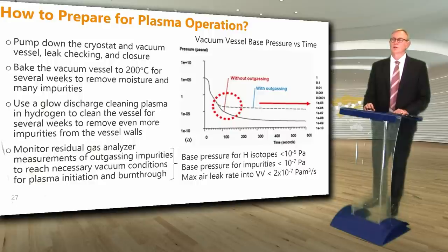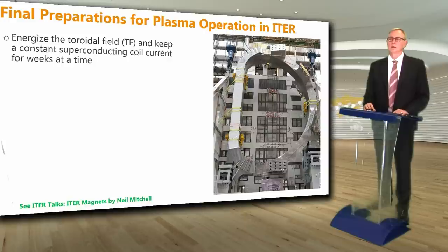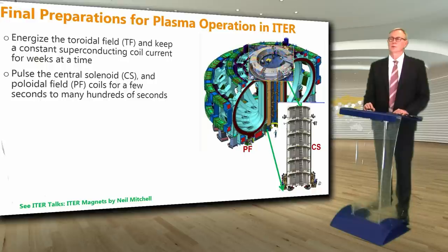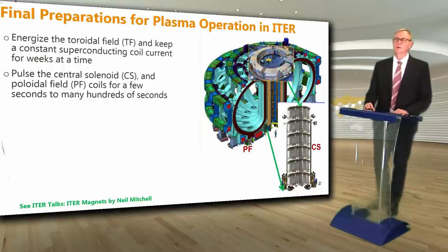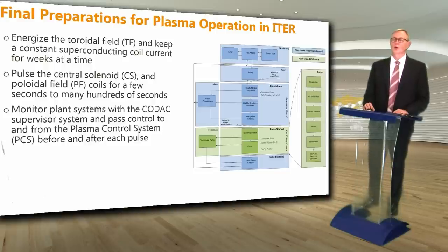This graph shows the vacuum vessel base pressure gradually decreasing with time as the vacuum conditions improve. The final preparations for plasma operation will be to energize the toroidal field and keep a constant superconducting TF coil current for weeks at a time, pulse the central solenoid and the poloidal field coils for a few seconds to many hundreds of seconds, and then monitor the plant systems with the CODAC supervisor system, passing control to and from the plasma control system (PCS) before and after each pulse.